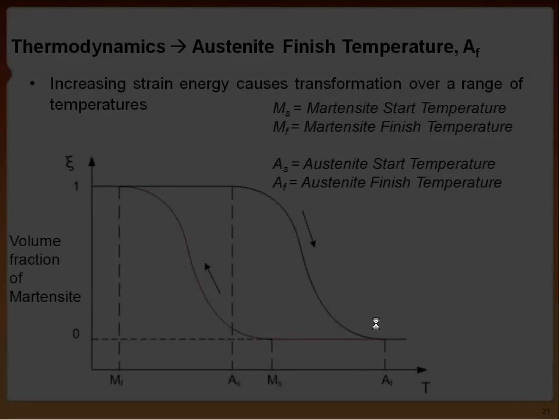So what this is exhibiting here is called a differential scanning calorimetry curve. For industry, this is what we mainly use when we examine bulk ingot or raw material. What it basically says is as we change the temperature of a sample, we can monitor the heat flow in and out of that sample. This gives you the most accurate transformation temperature of your material, but it doesn't say much about how your device will function at its so-called finish temperature. It gives you the finish temperature of a bulk ingot, but it doesn't really tell you that well how your device is performing at its AF temperature.